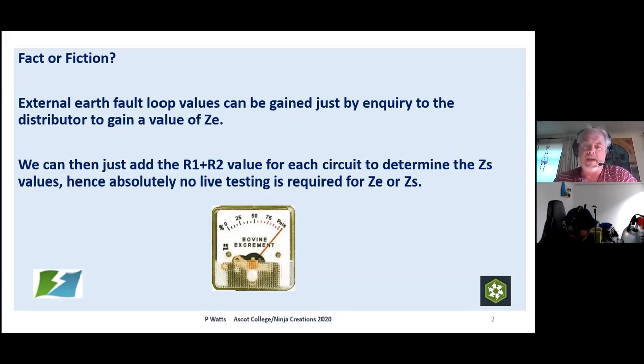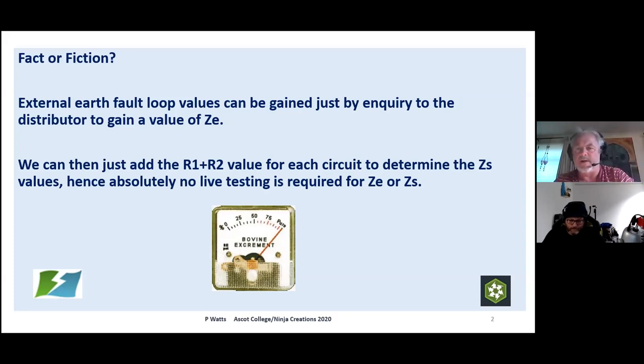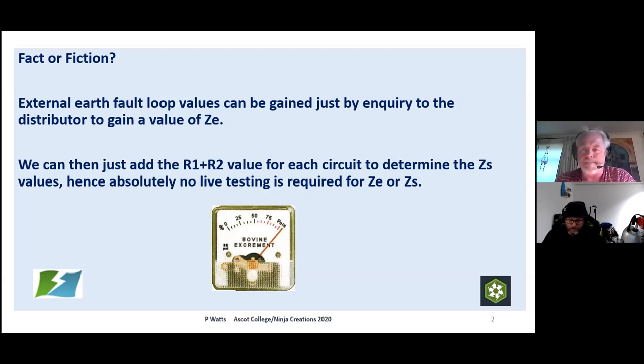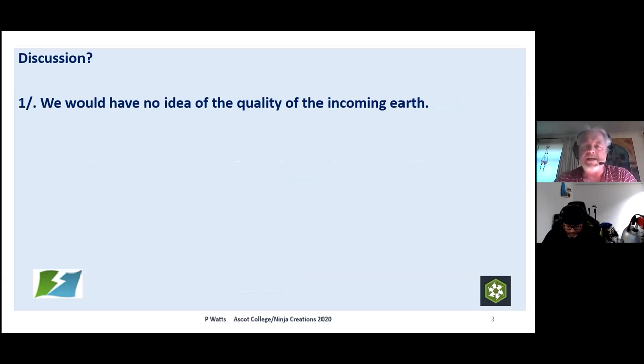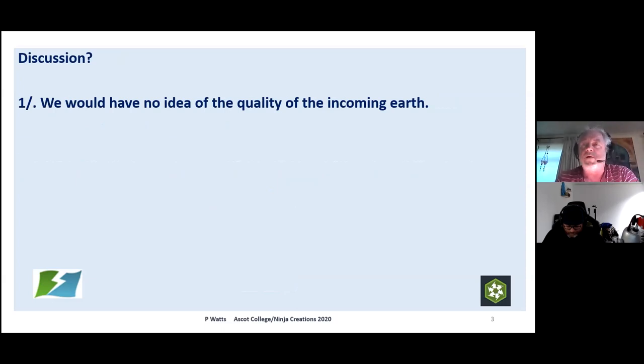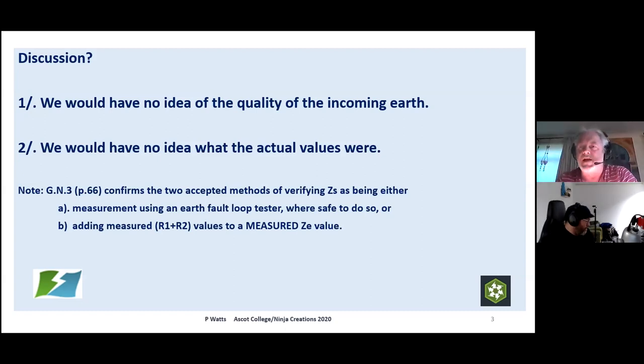To have an earth loop impedance by inquiry, and not test it, then do a calculated R1+R2 and add that on and say that's your earth loop impedance — I think is total nonsense, because at no point are we actually testing that we've actually got an earth coming in. If we know we've got a good earth coming in and then we do a calculation and add it on, that's slightly different. But doing one by inquiry — ring up, 'what's the earth loop impedance? Oh, it's such-and-such' — and not actually test it, and then add on by calculation and call that acceptable for a finished installation — I think it is wrong.